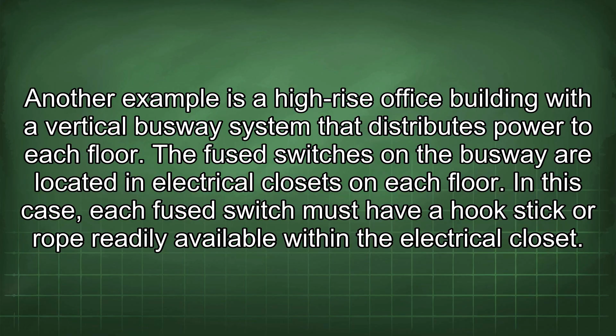Another example is a high-rise office building with a vertical busway system that distributes power to each floor. The fuse switches on the busway are located in electrical closets on each floor. Each fuse switch must have a hook stick or rope readily available within the electrical closet, ensuring building engineers can quickly and safely address any electrical issues that may arise.